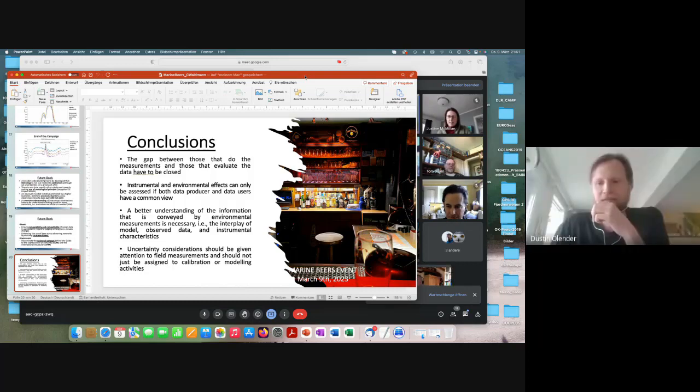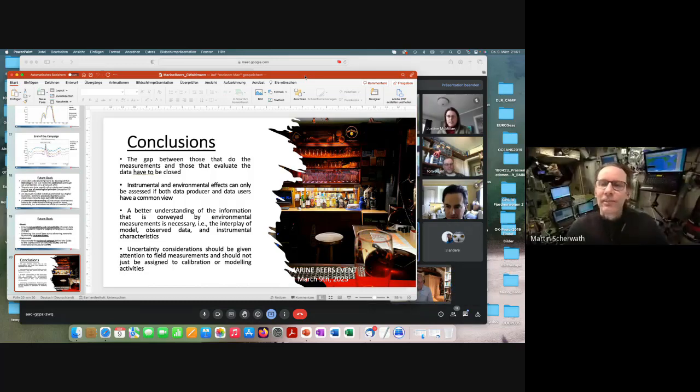Martin's got a question. Yeah, actually, I also have several, but I'll start with the most fundamental one, which is what we observe with our long time series at Ocean Networks Canada, where we do instrument changes on a regular basis just to get them ready for maintenance. And we do have jumps in the data when we come down with a newly calibrated instrument. So what's your recommendation on post-calibration and how to deal with these jumps, where you put in the best calibrated instruments that you can find, and then you deploy a new one and you get a different result at the same site when you swap?